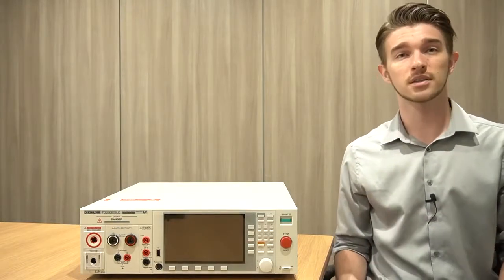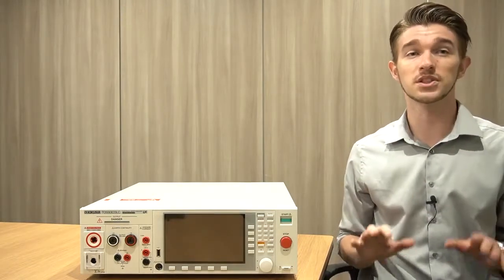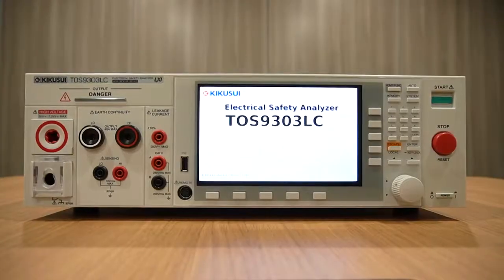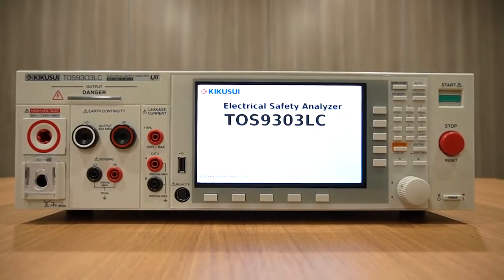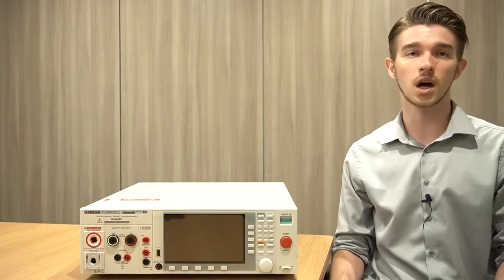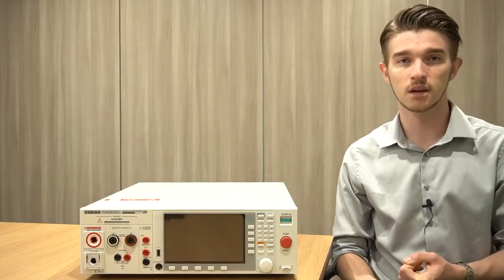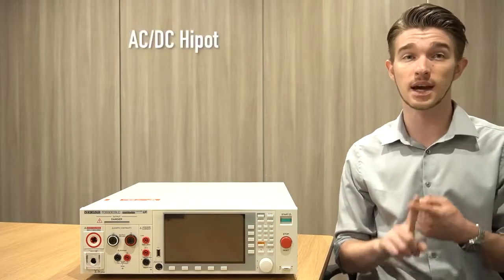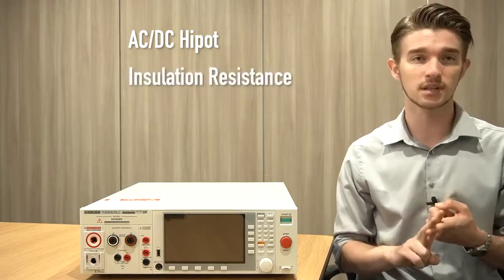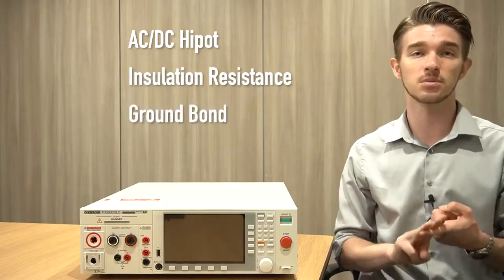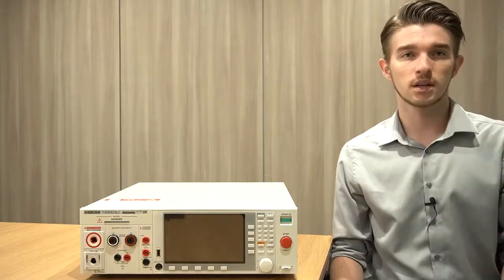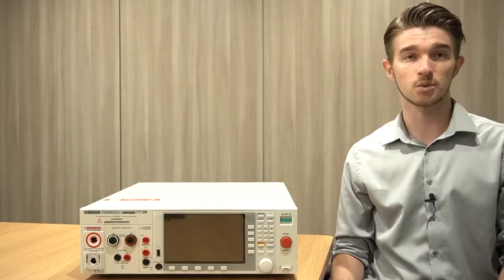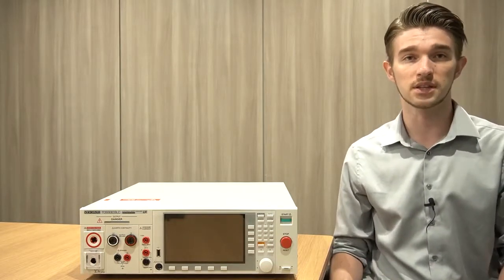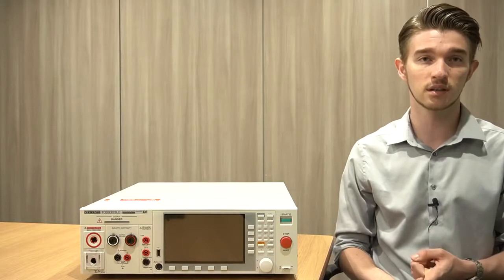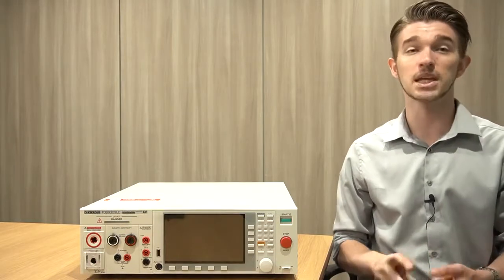Luckily, products such as the TOS9300 Safety Analyzer series by Kikusui Electronics offer an all-in-one solution capable of not only patient leakage current tests, but come equipped with AC and DC hipot, insulation resistance, and ground bond testing capabilities in a single unit. Conducting a patient leakage current test with the TOS9300 is as simple as setting test conditions, starting the test, and making judgments.